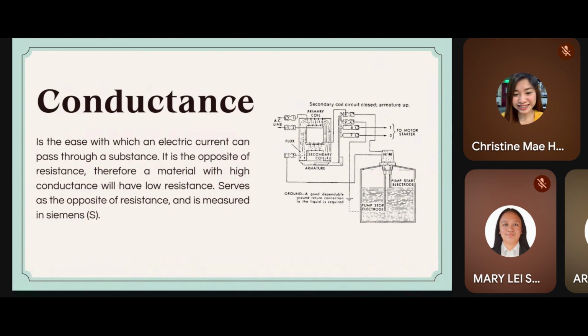Now, for conductance level measurement naman, it heavily relies on the electrical conductivity of the material. When the material makes contact between two probes or probe and vessel wall, it completes or breaks an electric circuit. It is best for liquids that are conductive, like water-based solutions. As for its applications naman, point level detection or high level alarm, pump control, or overflow protection, doon natin sila pinaka magagamit. For its real life uses, nagagamit siya most commonly in detecting water level in boiler drums, sewage and water waste level monitoring, preventing overfilling in storage tanks, and of course control system for pumps, start or stop operation when the level is reached.